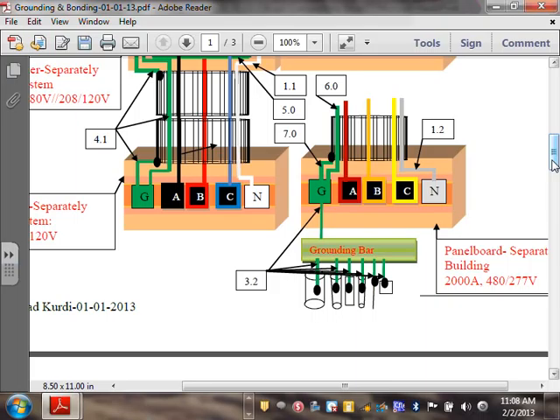Yes, sir. What if you came out of your CT cabinet and went to that second building? Then you would not need that ground? That's a new service. That's completely new. Then you don't need the equipment grounding conductor? Absolutely. You're not feeding from a switch here. You separated from the CT cabinet. You took two services, one to this building, and one that's a new service. Exactly the same. Start applying the rule of the 4,000 amp switchgear on it. Nothing really changes other than here's what really changed. You just want to bond the neutral to the ground here, in this case. Any comments, guys? Any questions? Does that make sense to all?